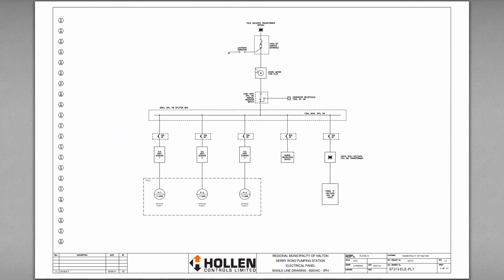So we had a pole mounted transformer coming into a power meter. There was an ATS with a generator receptacle. This panel just sits on the side of the road and it runs 3 huge pumps underneath the road. They built a kind of an underpass under the bridge. And underneath it, there's a huge stormwater containment tank that these pumps will run. So after a rainstorm like today, 2 of these pumps are running full out, probably moving 175 liters per second of water from there just to keep it passable by cars.